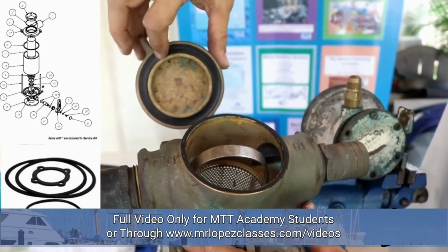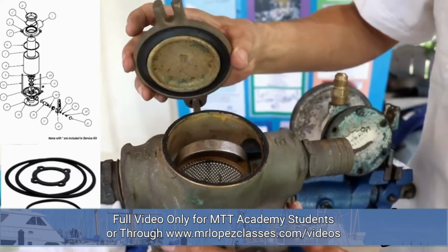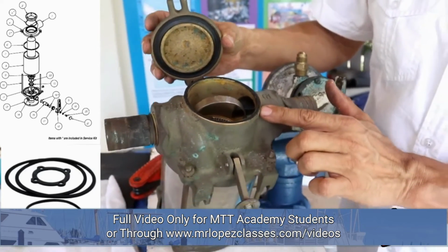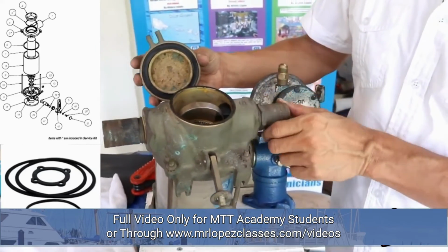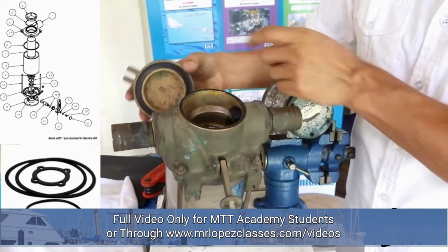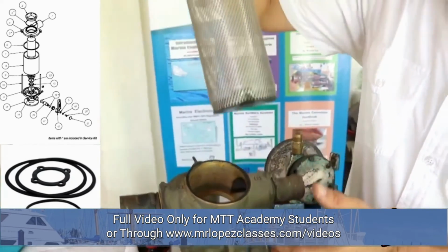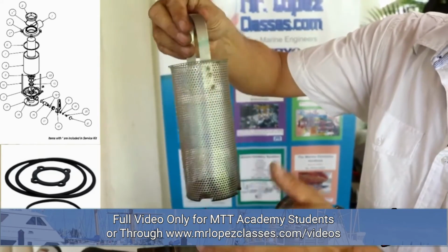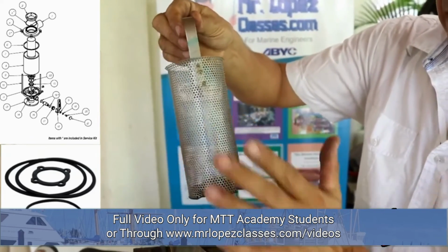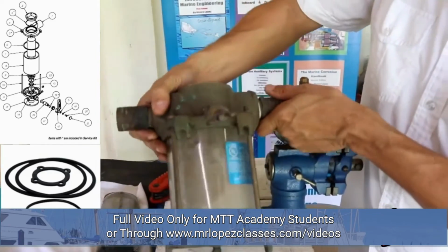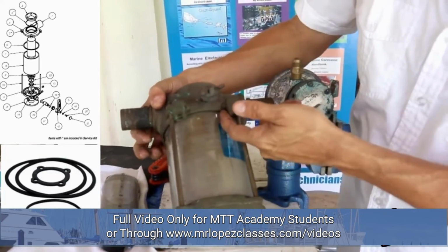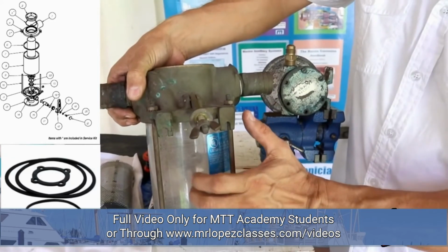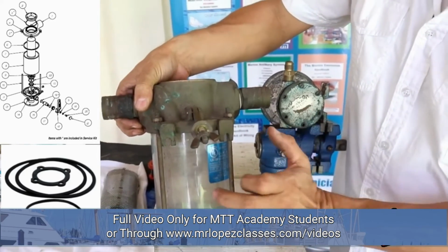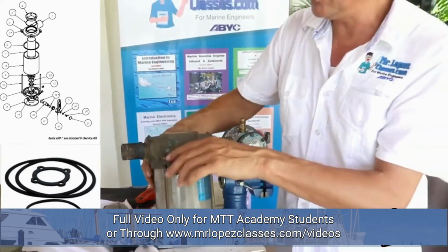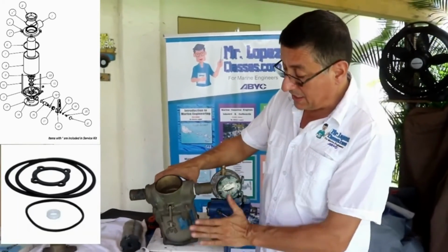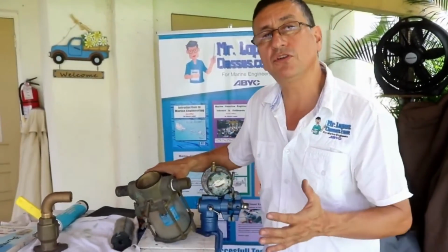You need to keep this gasket in good condition. You can order the kit in order to repair the strainer. The strainer is composed of the gasket, the basket, which is metallic in stainless steel, and the kit comes with two O-rings, one O-ring on top, another O-ring on the bottom, and with the crystal. In some cases, if you need to replace the crystal with a new one, it comes in the kit. The idea is to keep this strainer in perfect condition, completely clean.